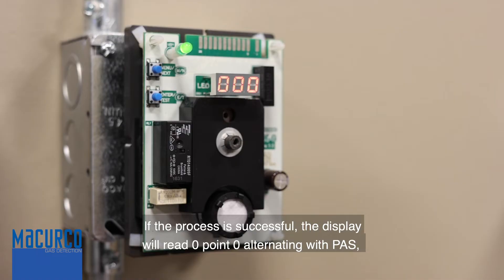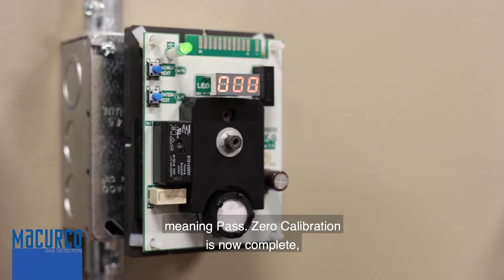If the process is successful, the display will read 0.0 alternating with PAS, meaning pass. Zero calibration is now complete and you are ready to proceed with span gas calibration.